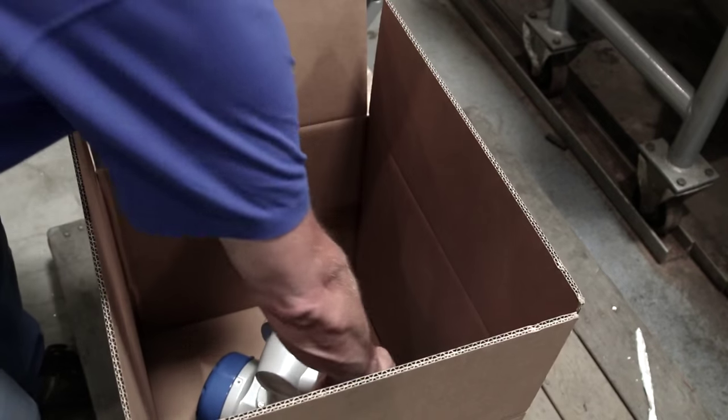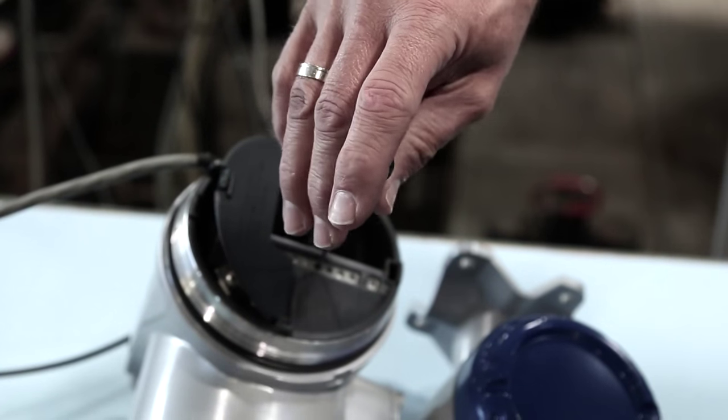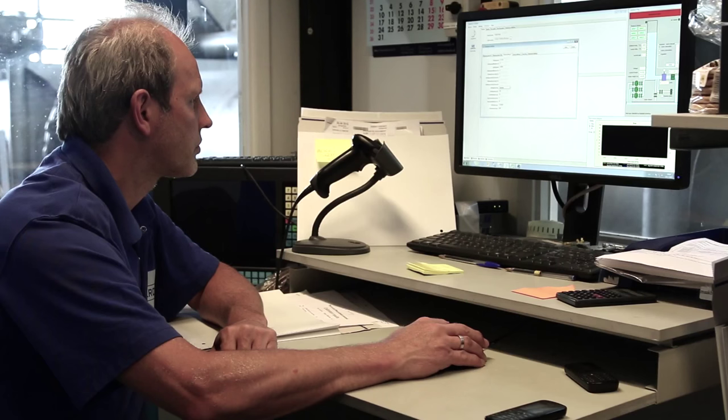After the last bolts are secured and the meter is leak-free mounted into the calibration rig, the converter electronics are being connected electrically to the calibration rig inputs. The converter is connected to the flow meter to measure flow during calibration, and a communication tool is connected to the internal bus for programming the calibration data.